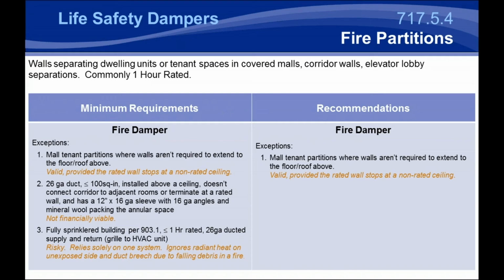Now, you can also install a duct that's less than or equal to 100 square inches. Of course, 26 gauge duct, so it's fully metal steel duct that has no flexible duct, in a subduct, that is a subduct in a sleeve that's 12 inches long through the penetration, held in place with 16 gauge angles and mineral wool between the annular space of the subduct and the opening. Now, the problem with that is that type of installation mimics a fire damper, and typically it'll be cheaper and easier to install a fire damper than to install this duct and subduct system.